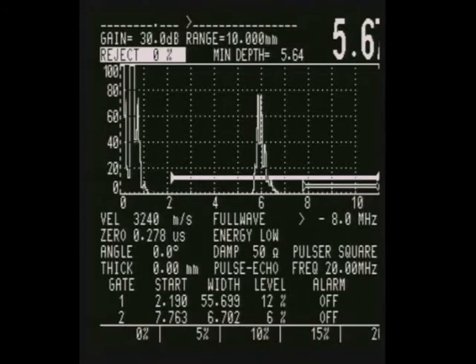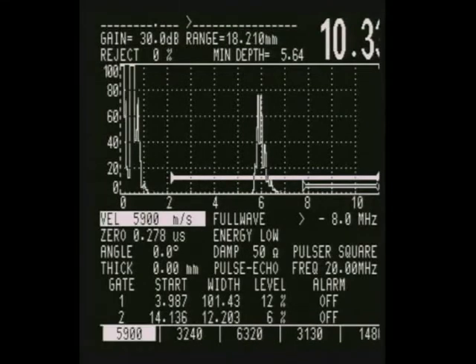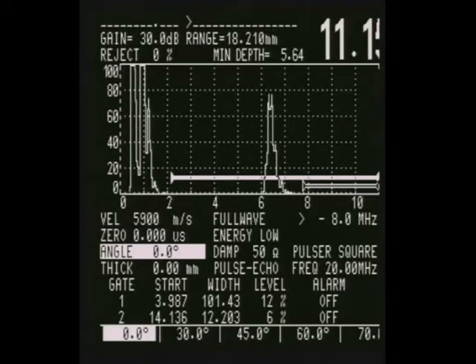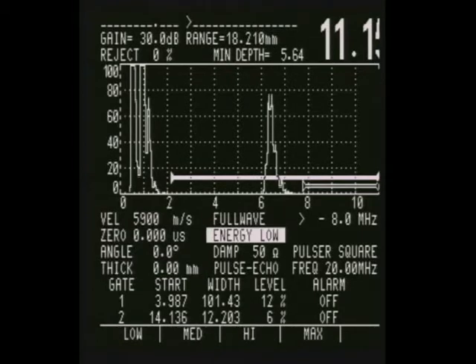Bring the range down to 10mm. Reject to zero. Velocity is at 3240. We're going to set that at 5900. Zero to zero. Angle to zero. Thick to zero. Full wave. Energy is low.